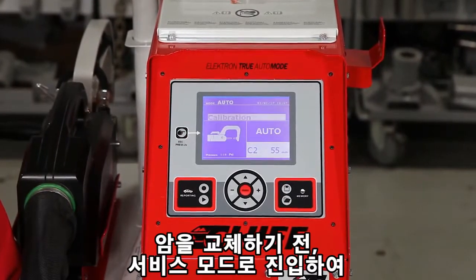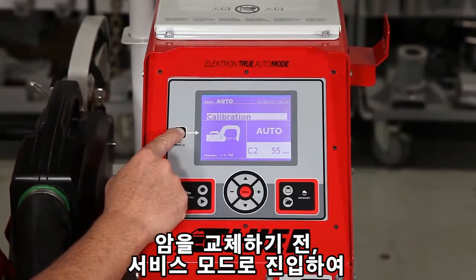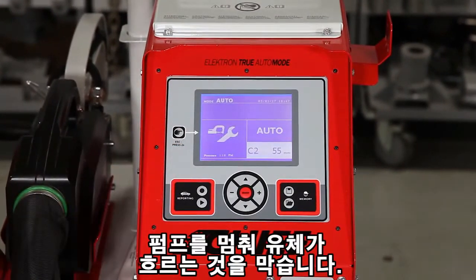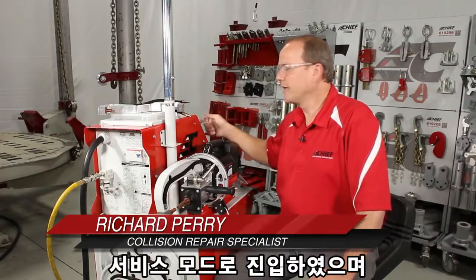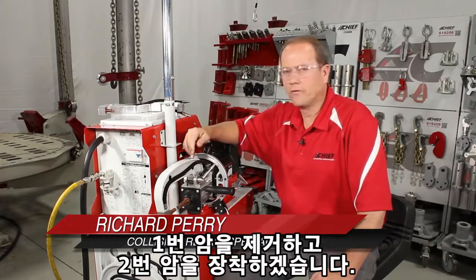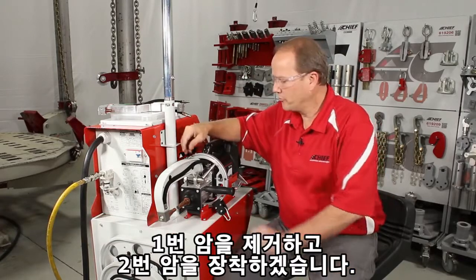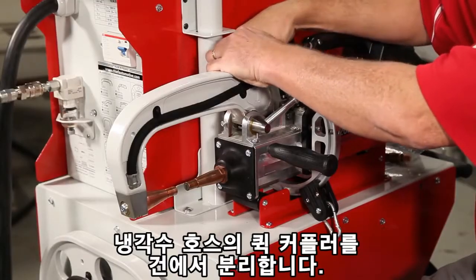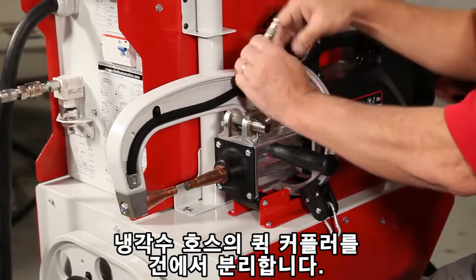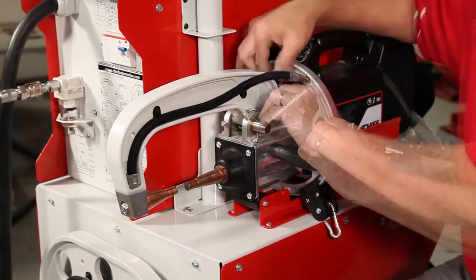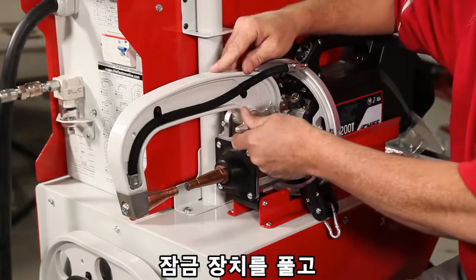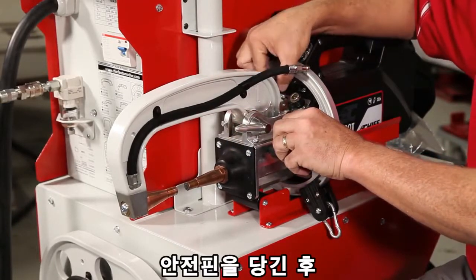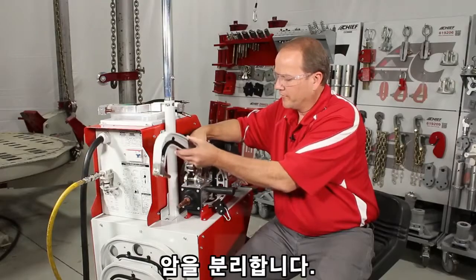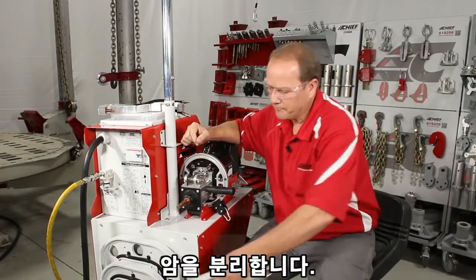Before changing out the arms, we must first put this in the service mode, stop the pump and the fluid from flowing. Okay, after putting it into the service mode, we're going to remove the number 1 arm and put the number 2 arm in. We're going to disengage the water lines by using the quick couplers, release the lock mechanism, pull the pin for the safety lock, lift the arm, remove it.